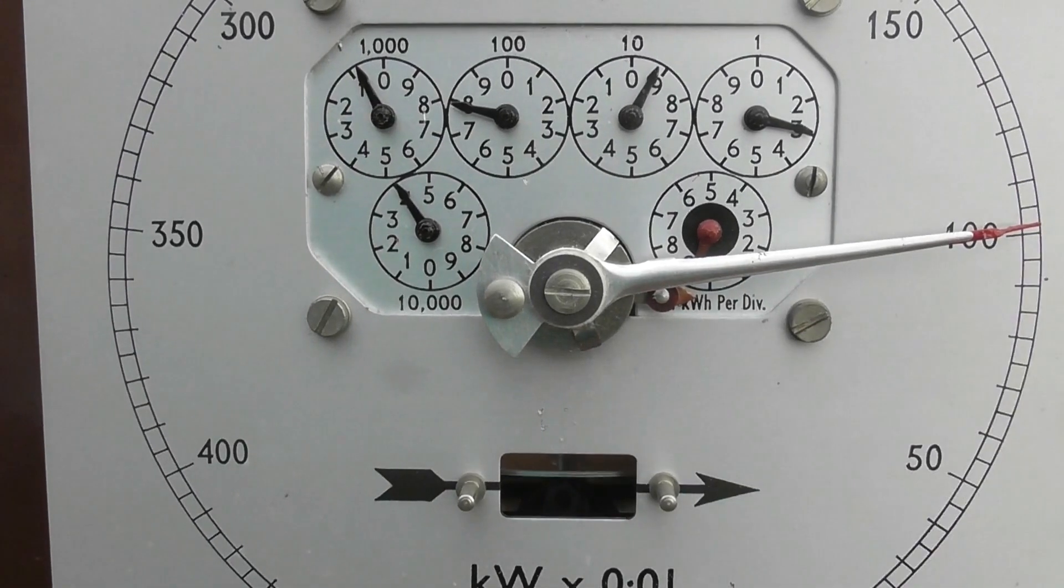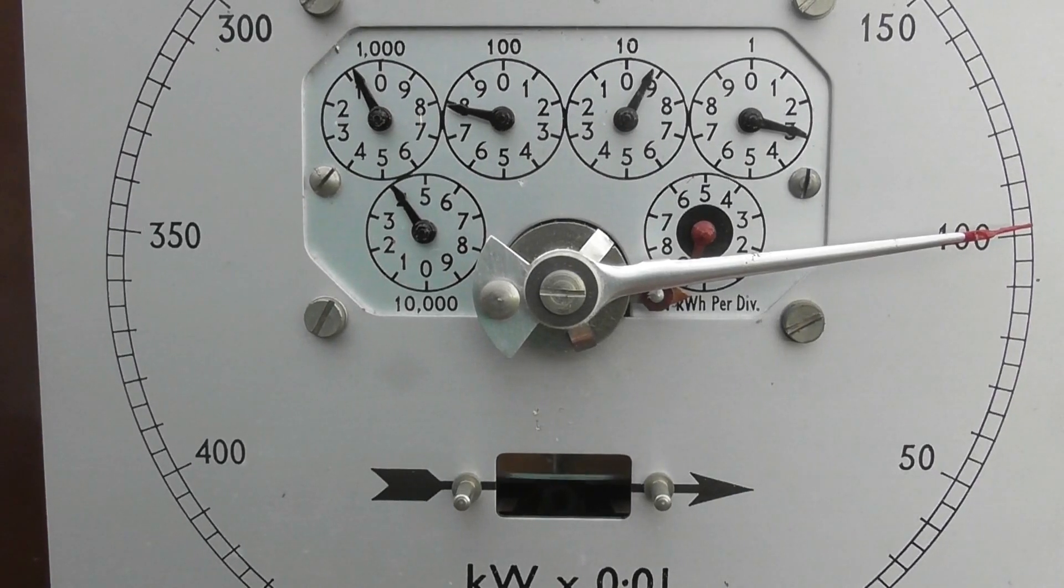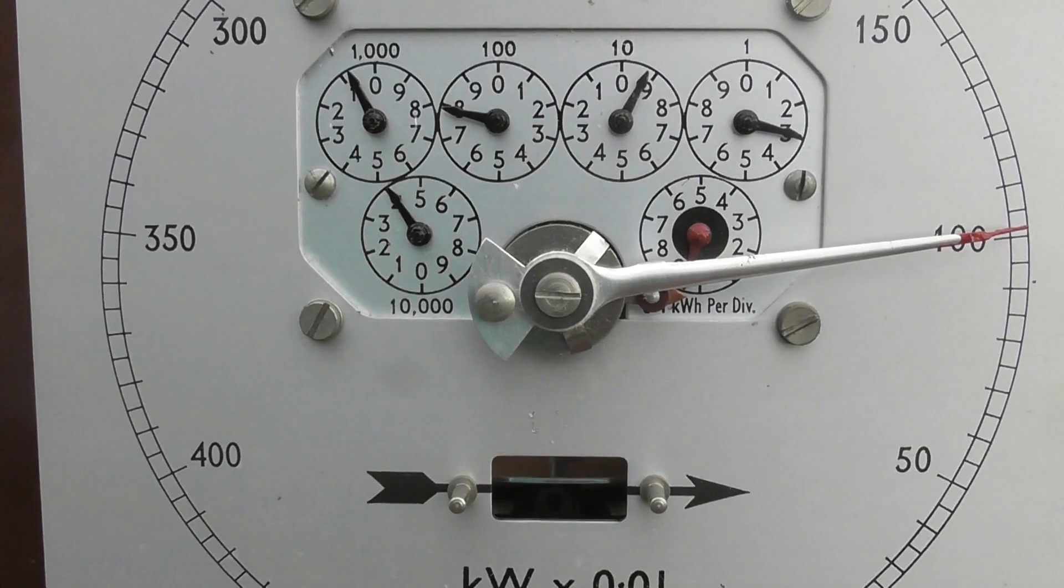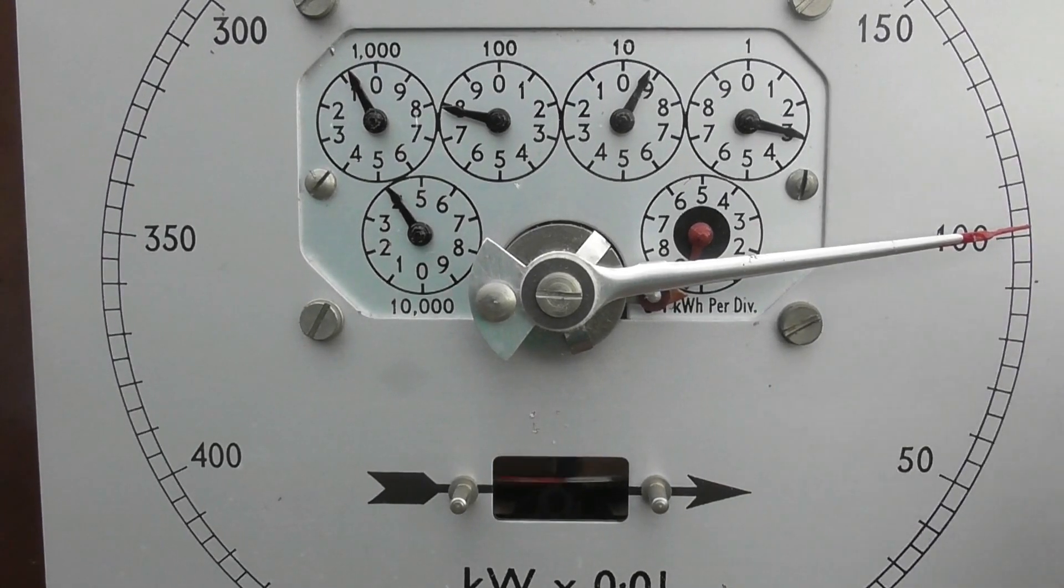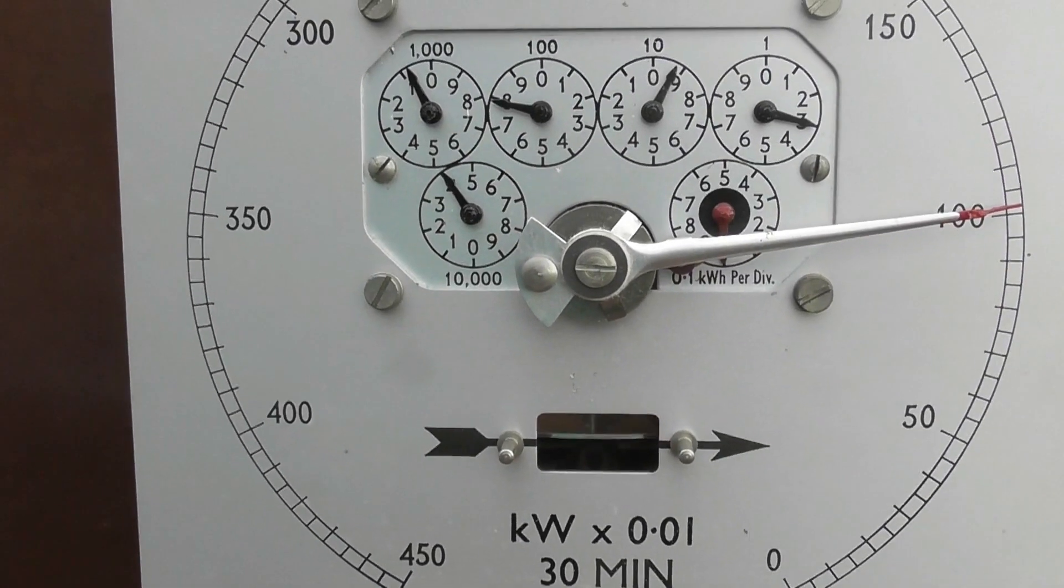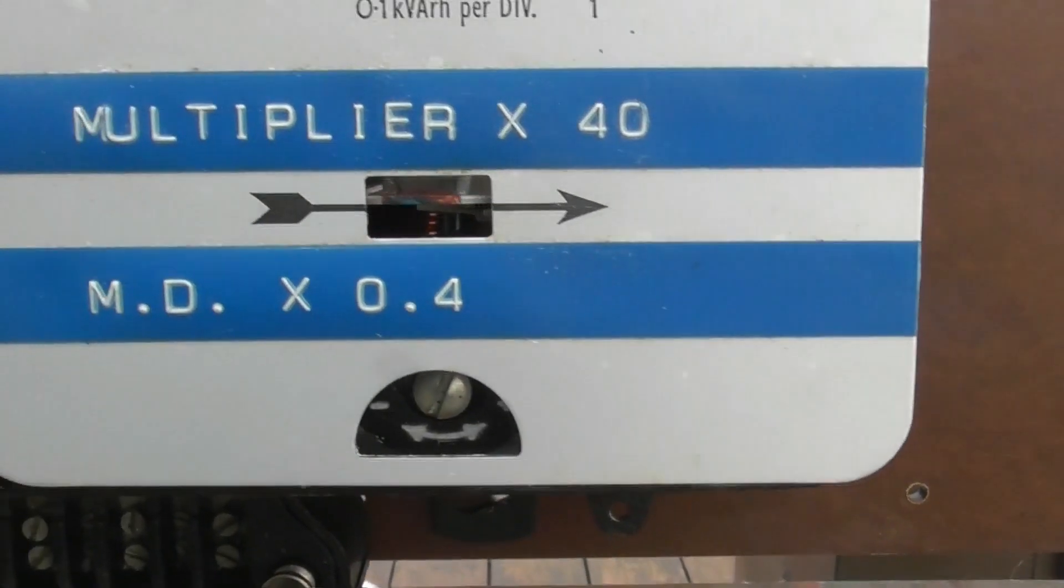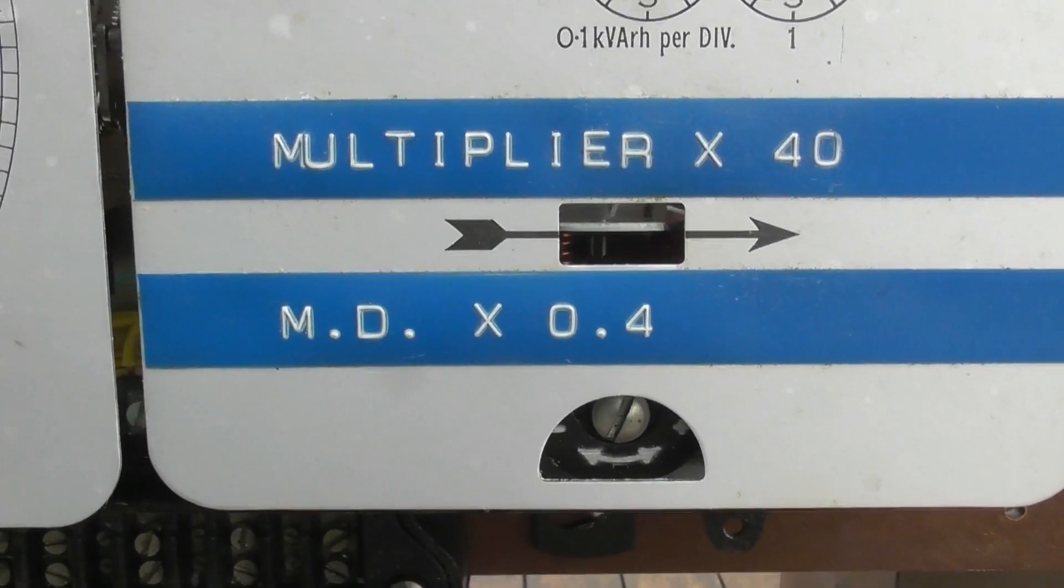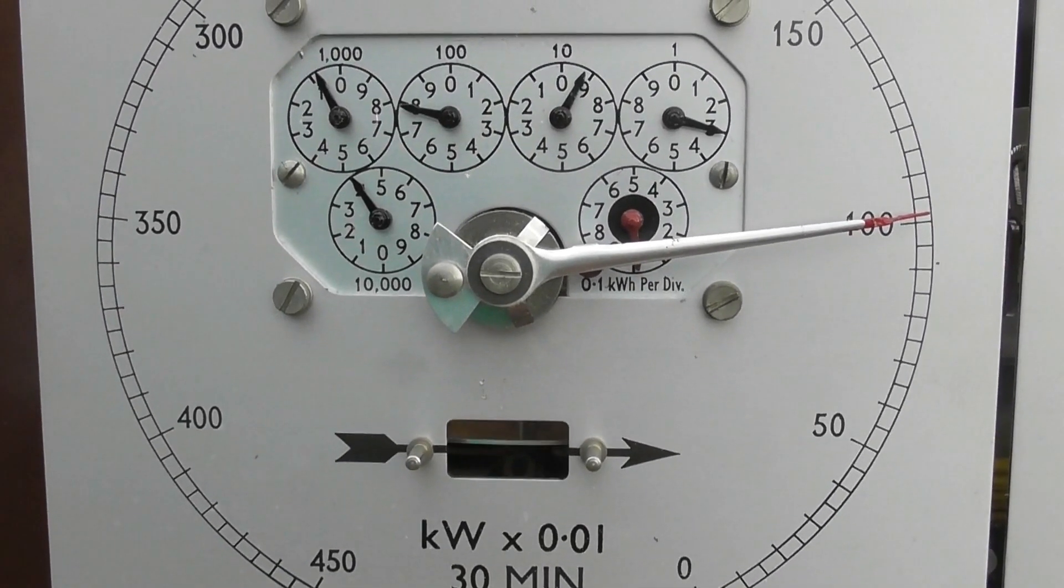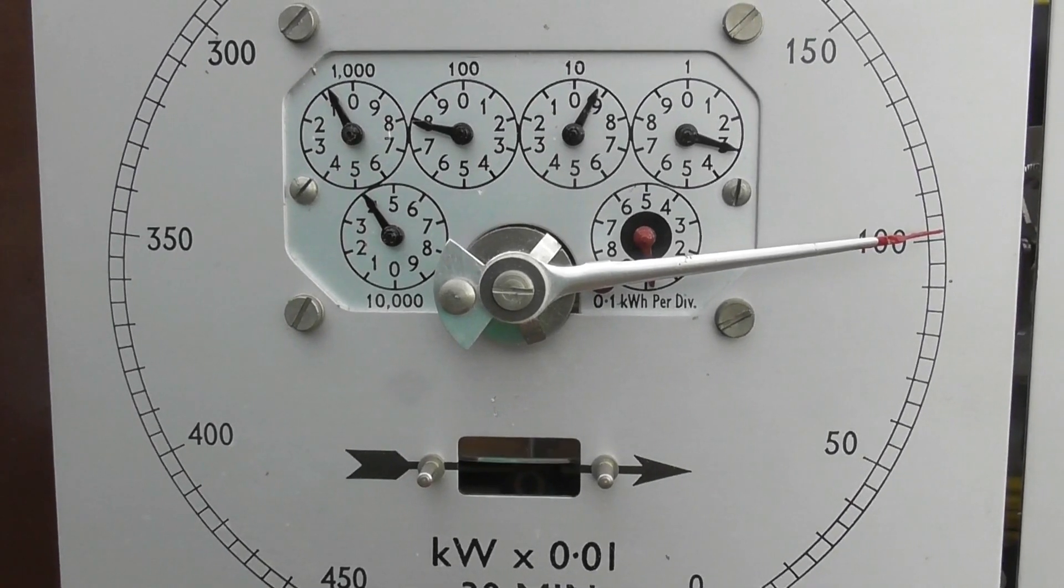The big demand pointer will remain where it is and then when the meter reader comes they can reset the pointer and take a note of the dial what it shows. Say for example this shows a hundred, one zero two or so. A hundred and the MDI is times 0.4, so if that meter shows a hundred, that would equate to 40 kilowatts.